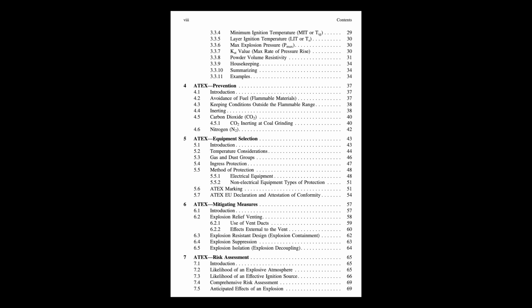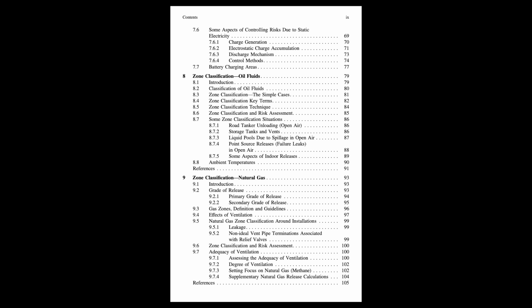That's the general principle, yes. You match the equipment's safety level to the zone's risk level. Our guide even gives specific examples for oil handling, like tanker unloading and tank vents, and also for natural gas. Let's touch on natural gas zoning. What are some key considerations there?